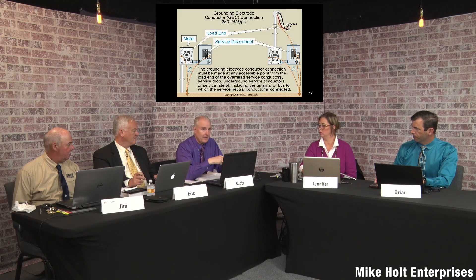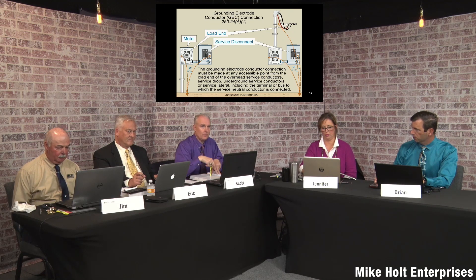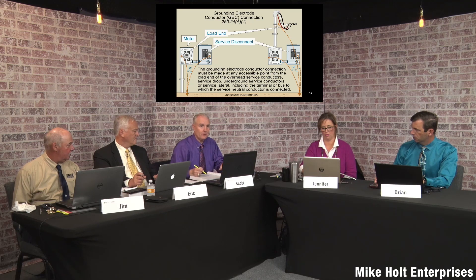I think it's a good idea, as we go through the next several parts, to highlight when it changes. You should highlight 250.24, and the next thing to highlight is 250.30 — that way you know if you're dealing with a service you're between 250.24 and the end of 250.24, and that's the only time it applies. So in 250.24 we're dealing with services.